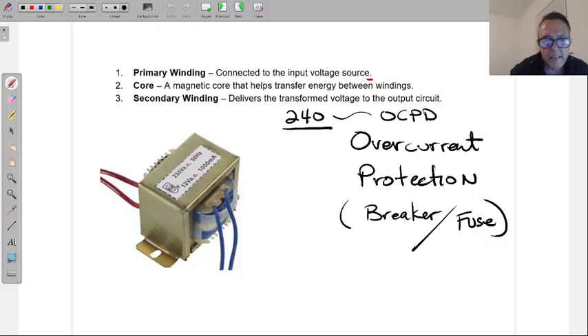What this is saying is this little transformer has to be grounded. All right, it's got to find a grounding system. You do have to protect the outside metal of the transformer. Now, this little one, it's not such a big deal. I'll provide some more pictures with this one when we get into the large three-phase transformers. But with the large transformers, the ones for power distribution in buildings, the grounding system gets very, very, very critical that it's set up correctly. I'll show you more images of that when we get into the three-phase transformers.